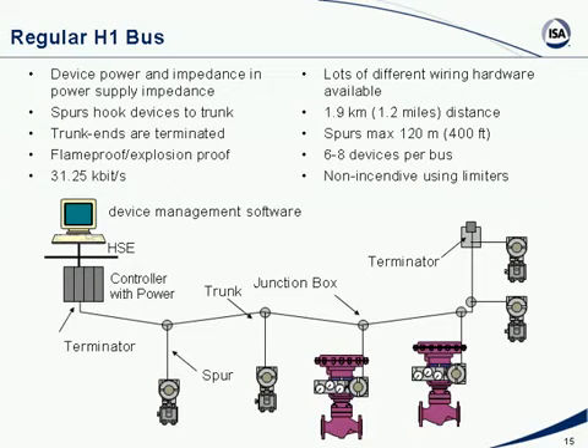For this kind of installation in Zone 2 or Division 2, what you do is you have a non-arcing trunk, and then you have current limiters in the junction box, so you get non-incendive spurs. This is very popular in North America.